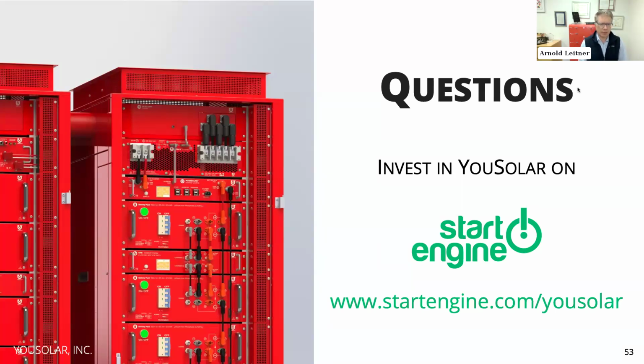Questions come up about the 3-foot requirement that might come around from energy storage systems, since AHJs adopt these rules on their own. To date, we haven't seen any pushback on the 6-inch spacing, but remember the PowerBloc is separable, so there's no problem putting 3 feet between the storage cabinets or any of those units. I'll also point out that I'm not aware - and I've asked a lot of people - of a single battery fire using lithium iron phosphate batteries, the chemistry we use.